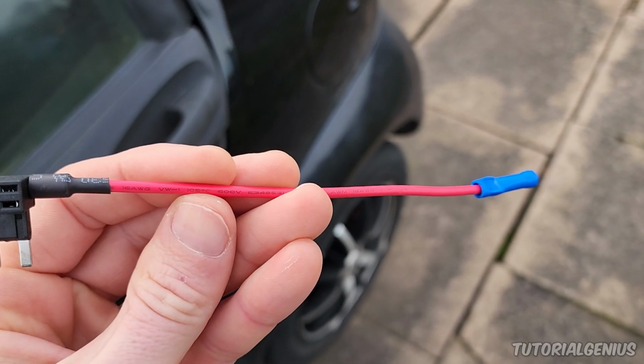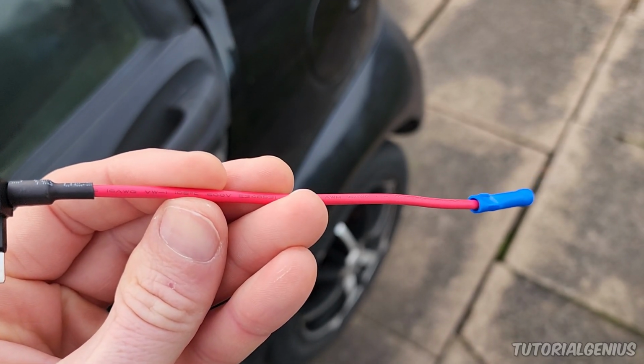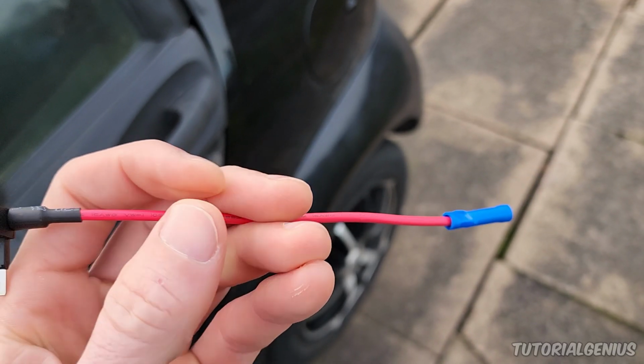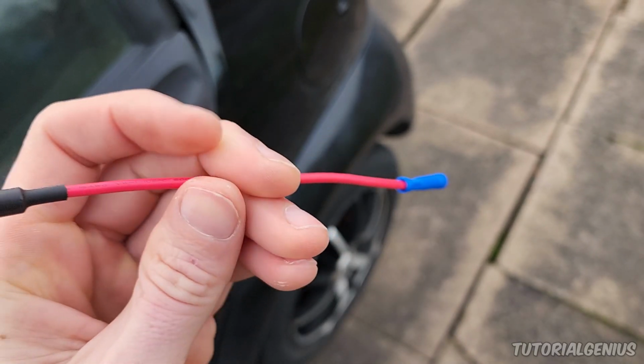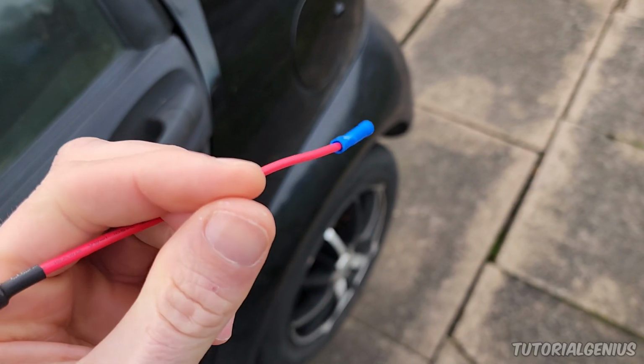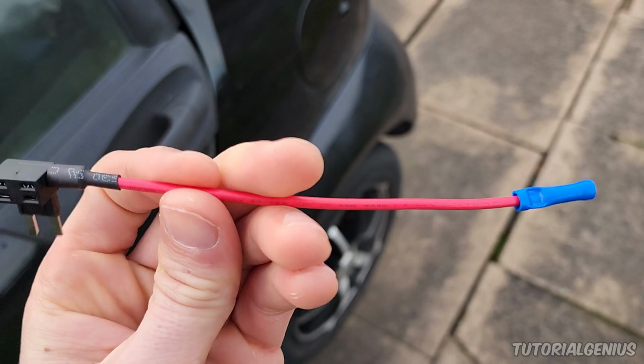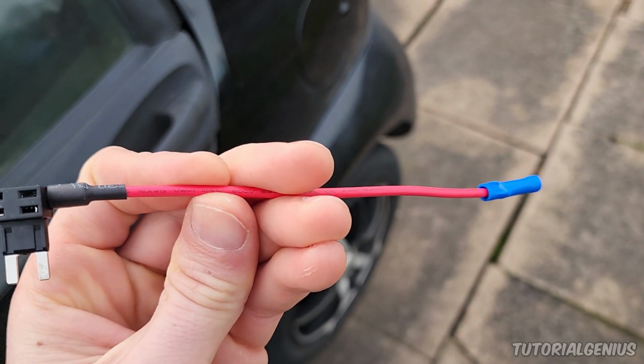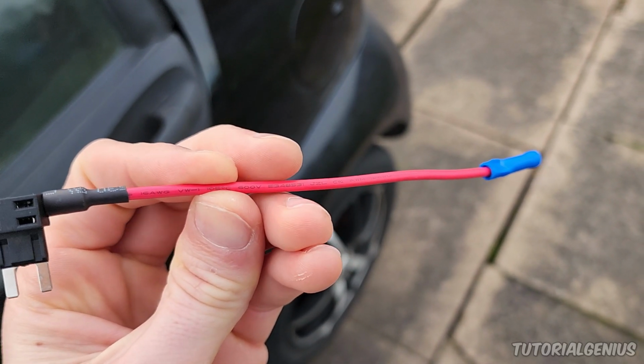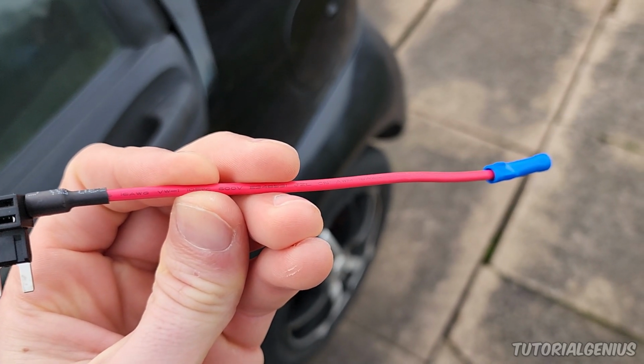A device that uses a lot of current, maybe a heater or a high-powered inverter, will generally have a thicker wire. The longer the wire, the thicker it needs to be as well, to allow for voltage drop. This is important when talking about why these aren't necessarily such a good idea.